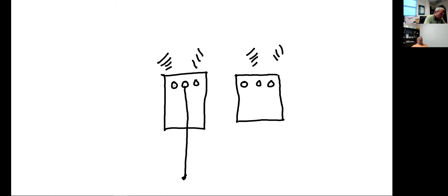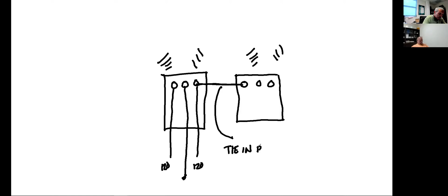1, 2, 3 bushings on a transformer. All right, I've got neutral, which is grounded. I've got 120 on one leg, and 120 on the other leg. The wire that goes in between the 2 transformers - anybody remember what that's called? Tie-in bus. That's what that wire is, right there between the transformers. Then I've got a wire that comes out of this transformer - this is my high leg, or power leg, same thing, one and the same. This goes to 7,200, this is grounded. This goes to 7,200, this is grounded. What kind of bank drawing do I have here?